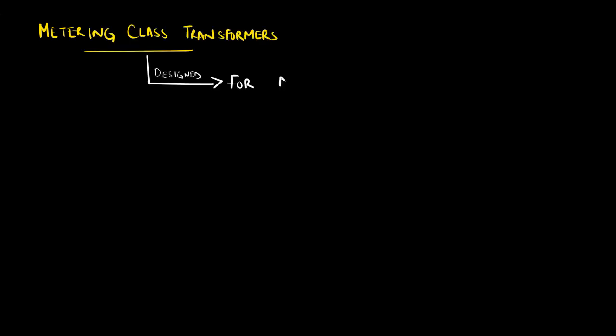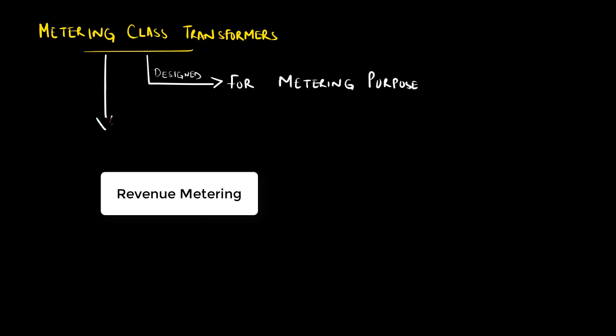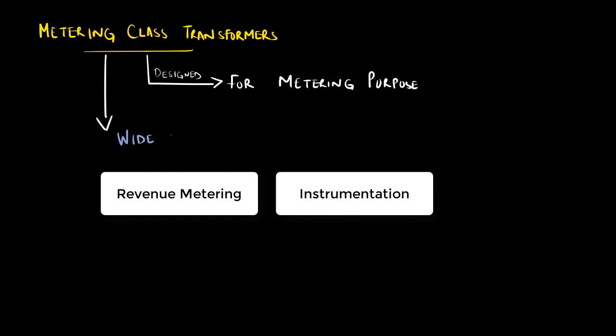It is important to remember that the metering class current transformer must be highly accurate, typically with less than 1% error at full load. Metering class CTs are used for revenue metering or instrumentational purposes.